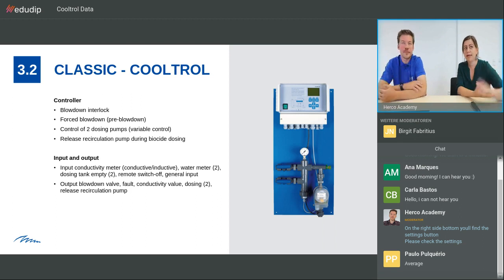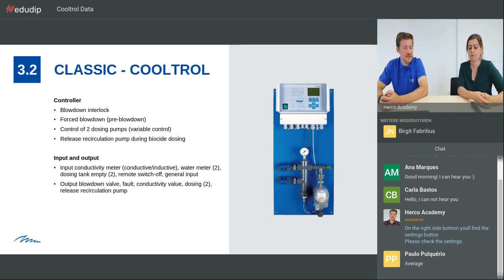To prevent this, or to already lower the conductivity, we use this forced blowdown, which is the second point, so that we can already reduce the conductivity before we start with the biocide dosing. We have here included already the control of the two dosing pumps. That means we have a timer included for the biocide dosing, and we get the signal from the flow meter on the makeup water line. And this signal is sent to the blowdown controller, and is going to be used in the blowdown controller for control of the volume control dosing, i.e. corrosion inhibitor in this case.